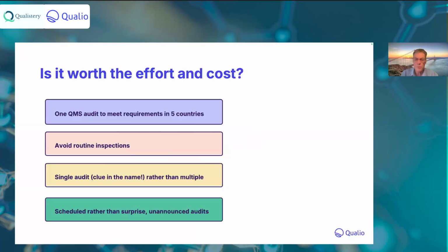MDSAP certification is slightly more expensive and challenging when compared to ISO 13485 alone. There are additional requirements in those 5 countries that need to be implemented as part of the quality management system, and those have to be audited by the MDSAP auditing bodies. But there are substantial benefits, given that only one audit is required to demonstrate compliance with several national quality management system regulations. The internal teams in your company need to prepare only once and support only one audit rather than doing that several times. And that saves considerable time and effort.